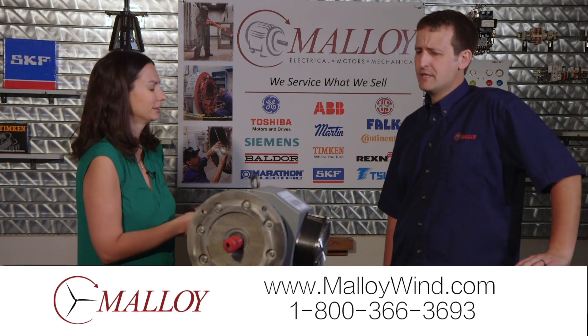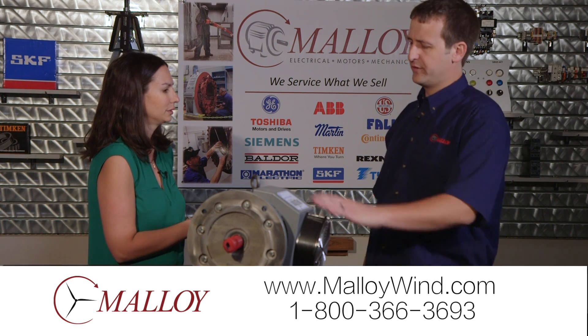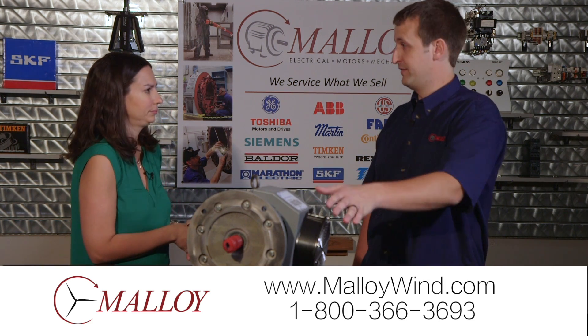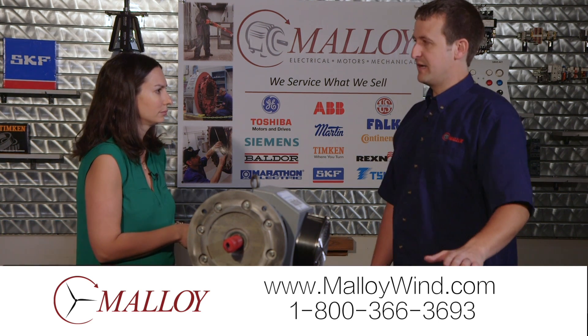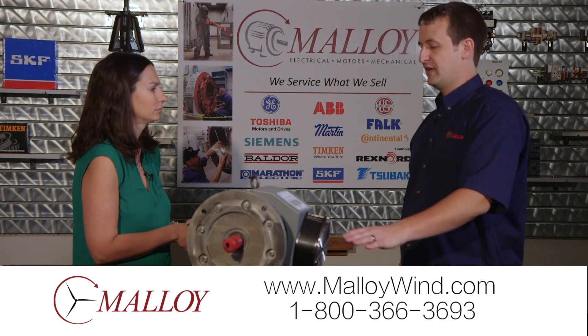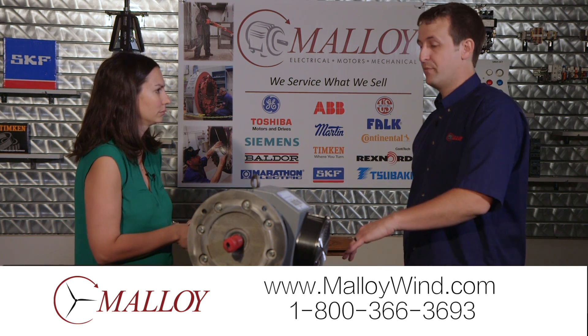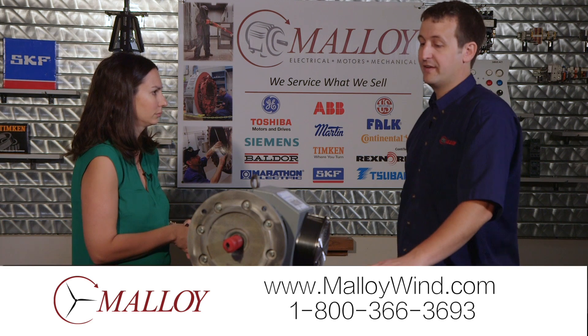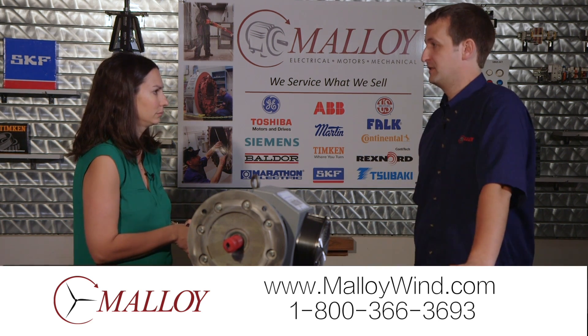There are two primary failure modes. Some of the older towers are only experiencing bearing problems — still difficult to get in and out, so it's a big problem for them. That appears to be caused by electrical fluting, and we're offering either a grounding upgrade, which will dissipate the current through a different path and lead to longer bearing life, or a ceramic bearing option which would do the same — making sure they don't fail the bearings.